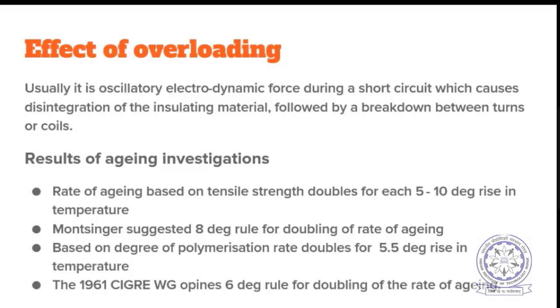So I was saying that it is usually due to electrodynamic force, the sinusoidal force that exists between the coils or between the turns, and that occurs during a sudden short circuit. That force is a bit higher than normal, but the insulation might have already thermally aged or lost its mechanical strength and cannot sustain this force, and this force will disintegrate it, and then it may result in breakdown due to electrical voltage. So the first reason is mechanical, losing the mechanical strength, followed by electrical breakdown. That is the usual mode of failure of any transformer.